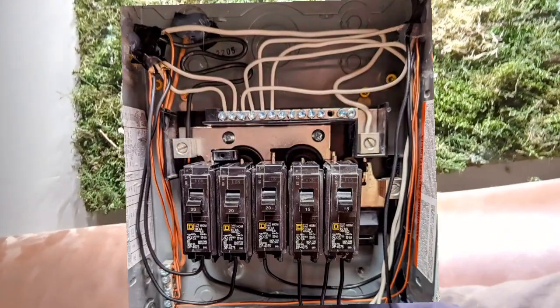So in this video, I'm going to be wiring up a 120 volt single phase sub panel box. Now, if you want to do 240, it's going to be almost identical to what I'm doing here, except you're going to have one more wire coming in, another hot wire. Usually it's a red, a black, a white, and then of course your ground. So really it's four wires, but they call it three wire.